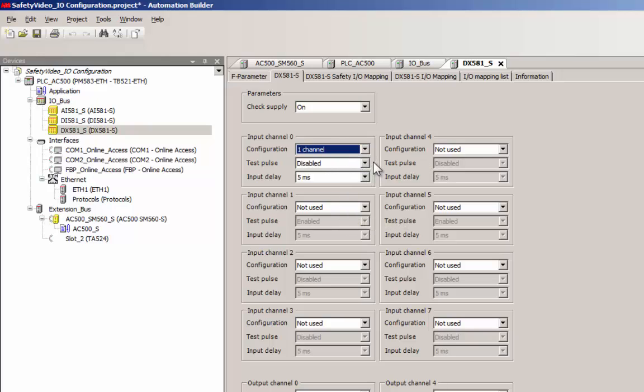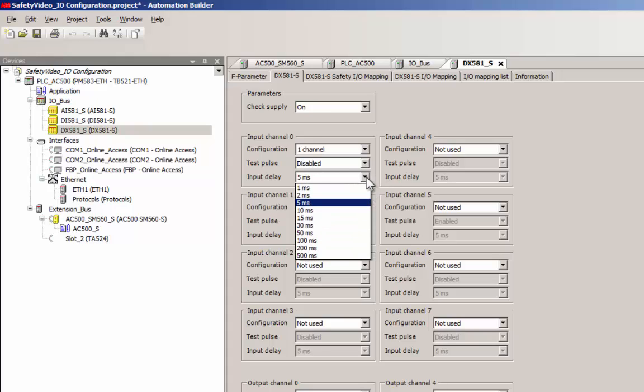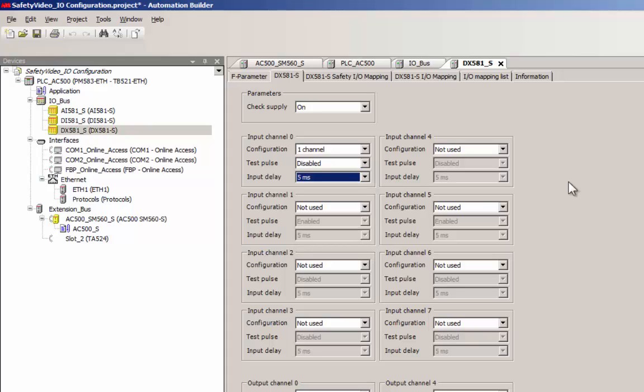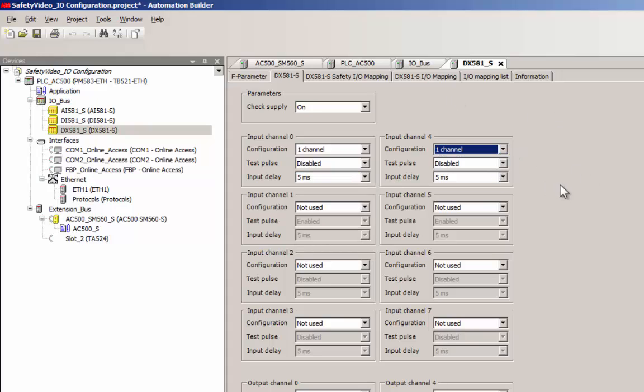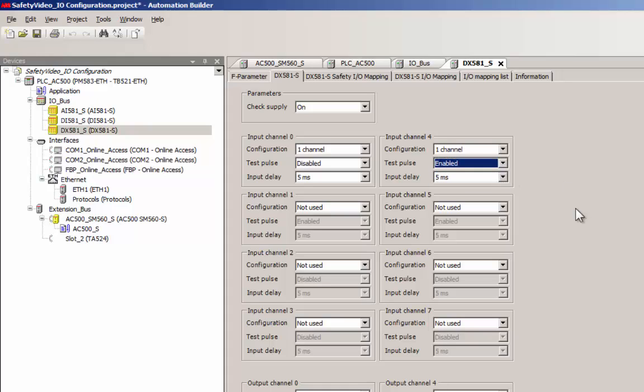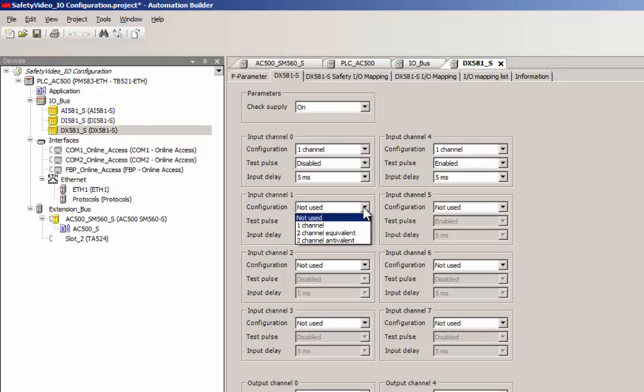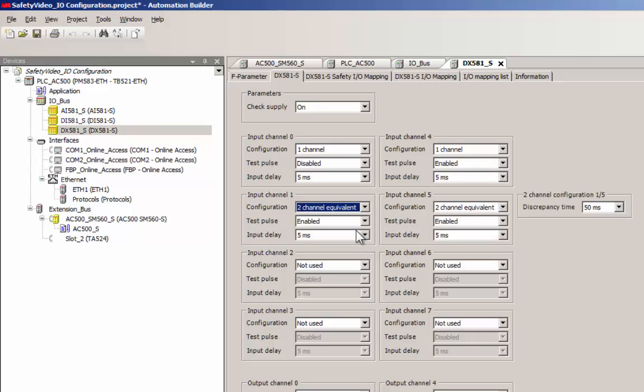Digital input channels could be configured as one channel or two channel type. In a two channel configuration, we need to choose the channel type, either as equivalent or antivalent, depending on the sensor or switch connected.